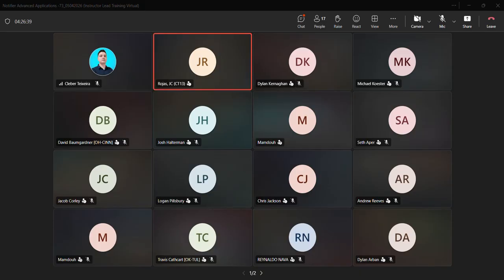Oh, okay. Gotcha. But Dylan, you said something? In Canada, I don't know if it's the same in the States, but a lot of the bigger buildings with the DVCs will all have 2-stage pull stations. So when a pull station's hit, it'll go into alert for a certain amount of time, and if no one acknowledges it, then it goes into evac. Yeah, Canada has that 2-stage, 3-stage thing.